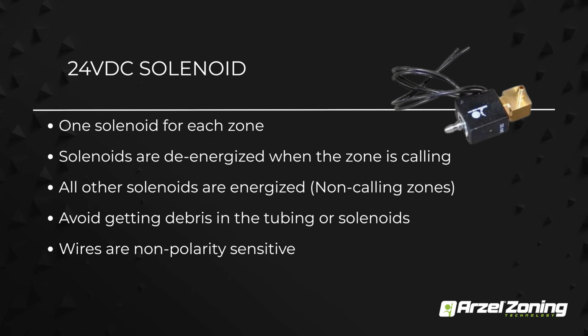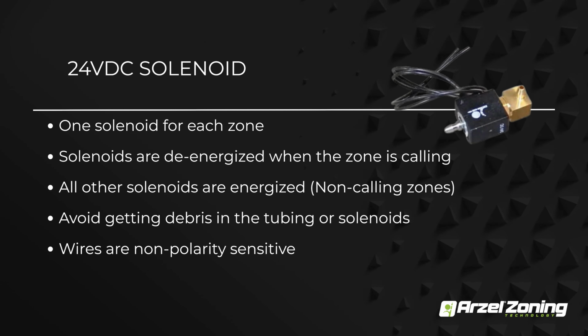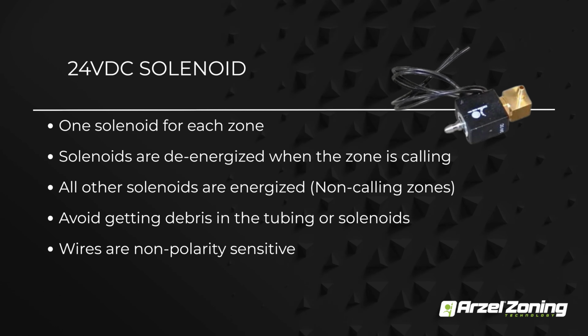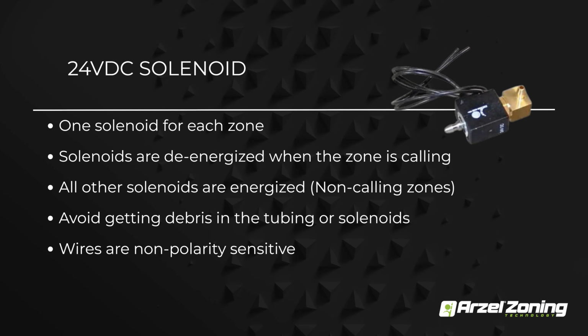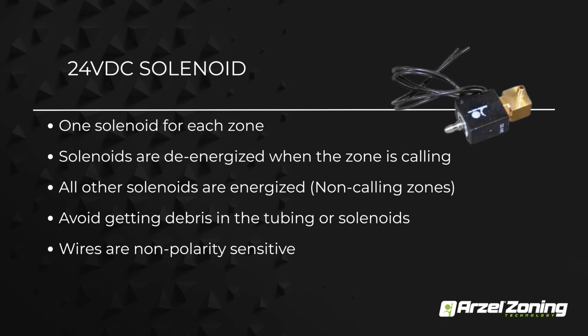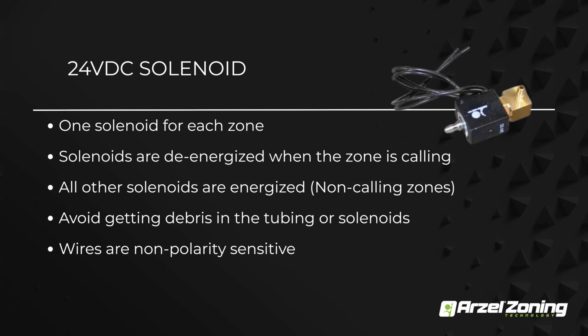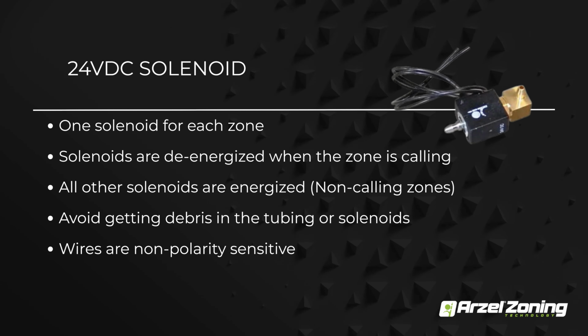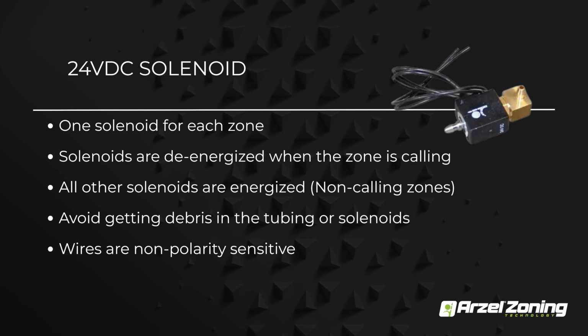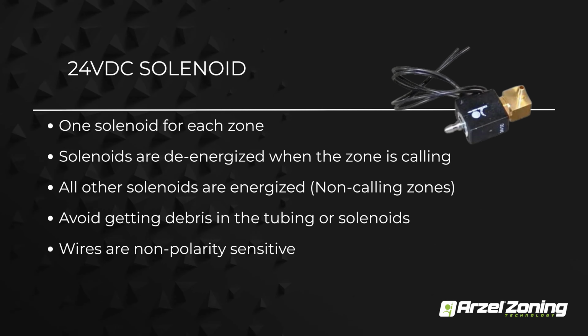Then along with that are our solenoids. You'll have one of these per zone. These are what is actually going to send the vacuum or pressure to your damper. So if there is a call on the system for conditioning, it's going to open the vacuum side of the solenoid to your dampers and open the dampers. If you ever get into troubleshooting these, we do a webinar on that as well. But just remember, the wires are non-polarity sensitive, so it doesn't matter which wire you have on what terminal, just that it's on the correct number. On every board, you're going to have a plus, which will be your common, and then a number per solenoid. Just make sure they line up to the number on the panel. Other than that, it's 24 volts DC to close dampers and 0 volts DC to open.